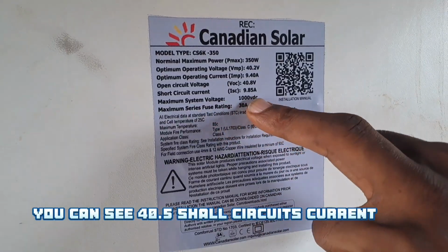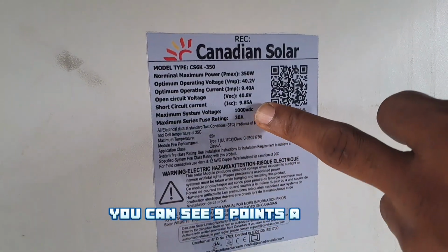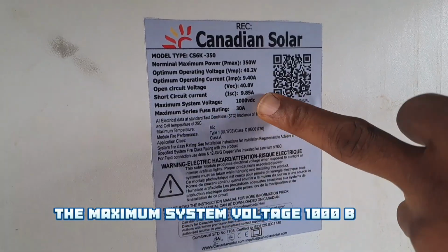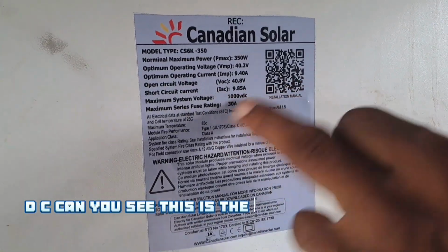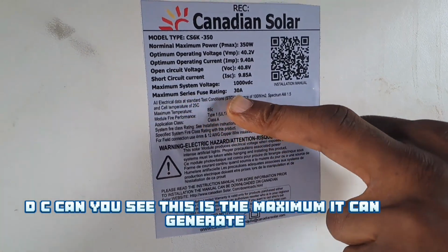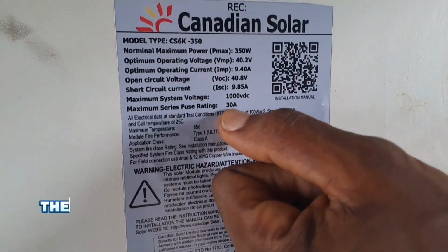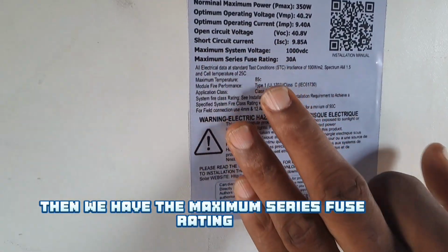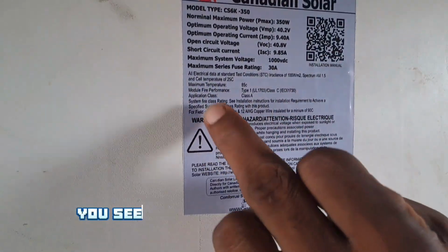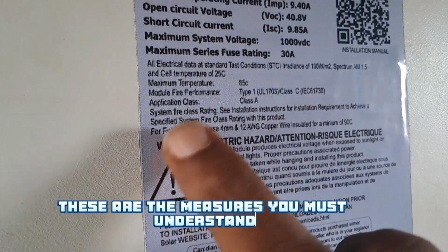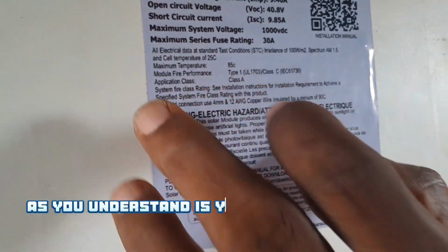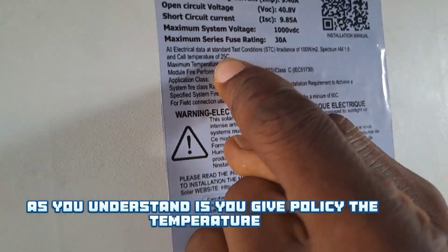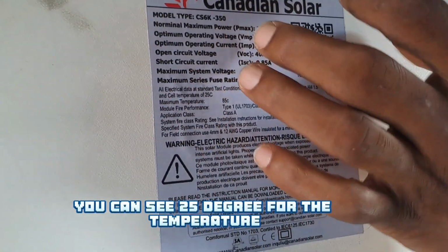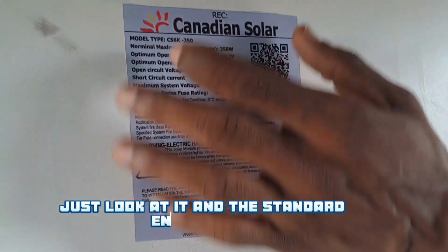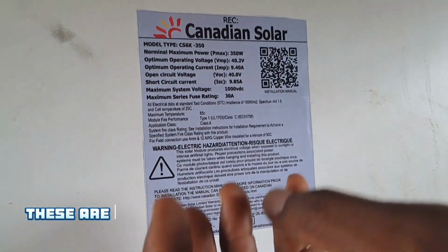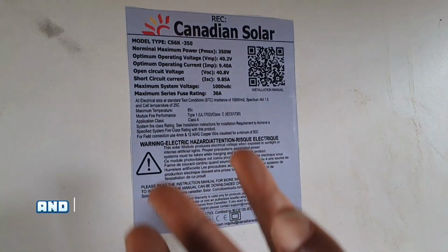Then this is the optimal operating voltage 40.2, optimum operating current 9.4, open circuit voltage you can see 40.8, short circuit current you can see 9.8, the maximum system voltage 1000 VDC. Can you see? This is the maximum it can generate. Then we have the maximum series fuse rating. You see the protective device. These are the measures you must understand.